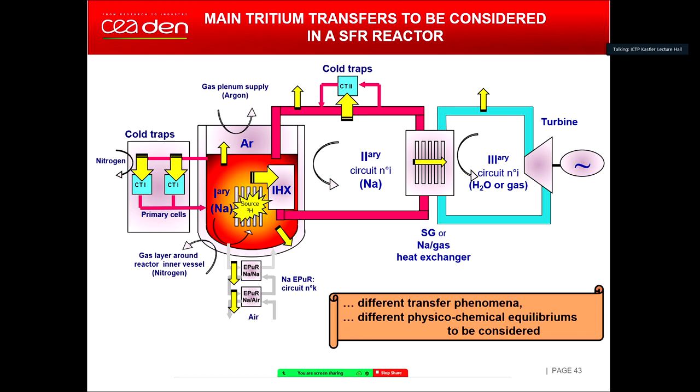And one part also of the hydrogen and tritium, you know that there is an equilibrium at the free level of the sodium in the pumps, secondary pumps, for example. You have what we call Sievert's law, an equilibrium between the liquid phase and the gas phase, and some hydrogen and tritium go from the sodium bulk to the gas. Okay, and so here you also have a possibility of a transfer of tritium from the secondary circuit to the water side and to the environment.